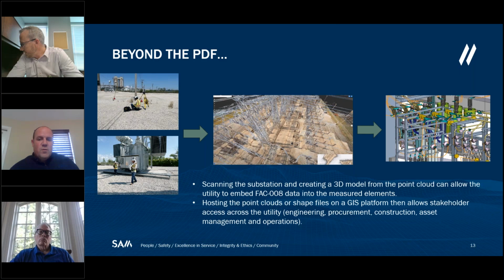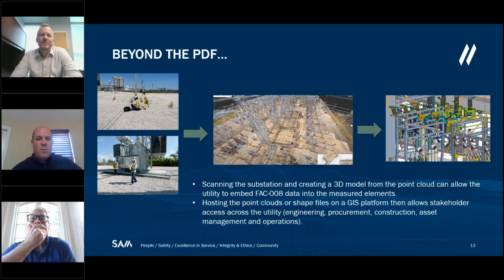Josh, one other thing on this — this is a good method for incorporating the FAC-008 data, not only to know where your most limiting component is so you can get it replaced, but when you decide you need to put more through the substation. Say you find your most limiting component is 795 ACSR. By adding the conductor type and ampacity as an attribute to those lines, you can filter out everything but your most limiting component and immediately know how much conductor you need to replace — say, 1431 ACSR.